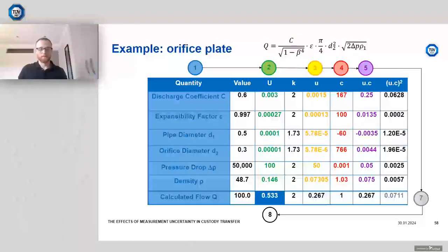So there's just as much a probability that it's right on the limit of this tolerance, or it's right at the value of 0.5. So we're reluctant to take any credit that there's more of a probability that it's at the middle of a normal distribution as opposed to a rectangular distribution where it's on the edges. So instead of dividing by 2, we divide by root 3, which is 1.73.